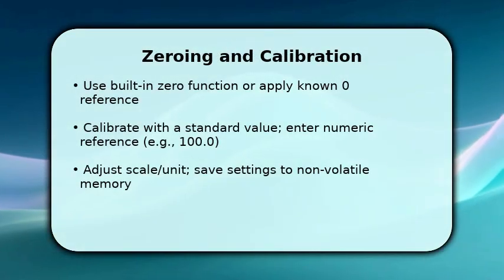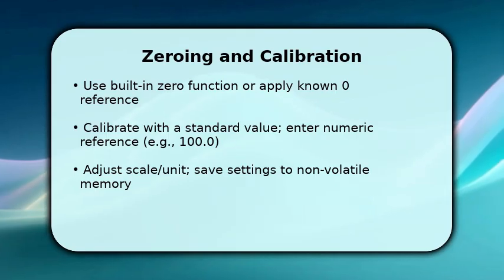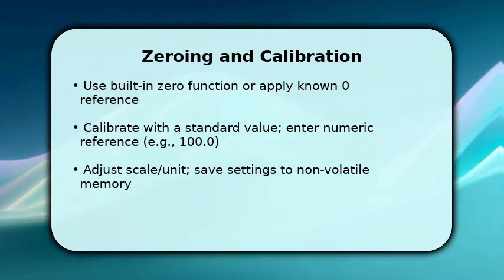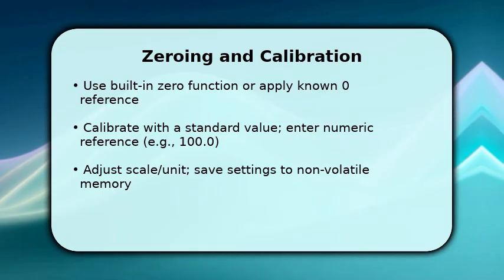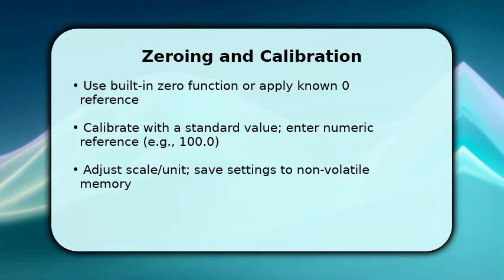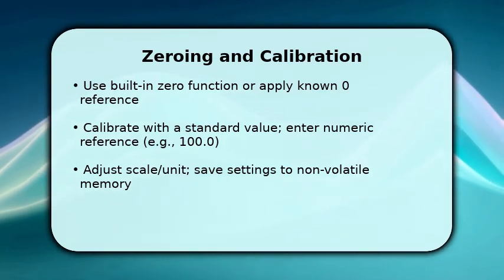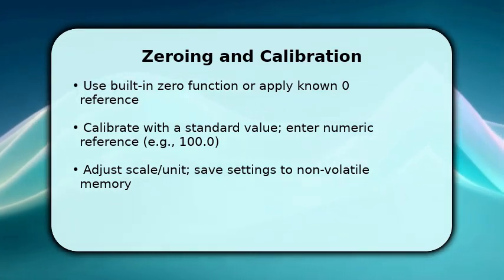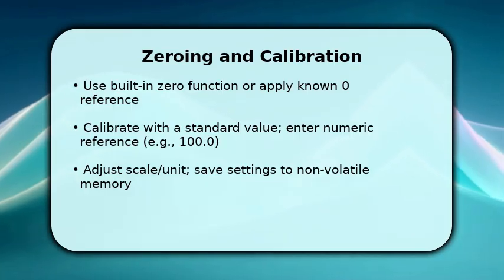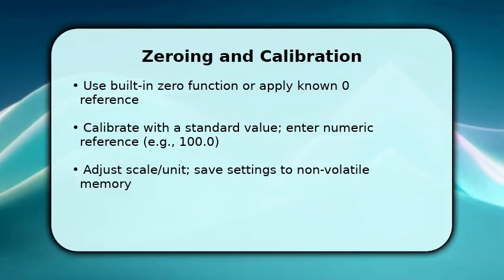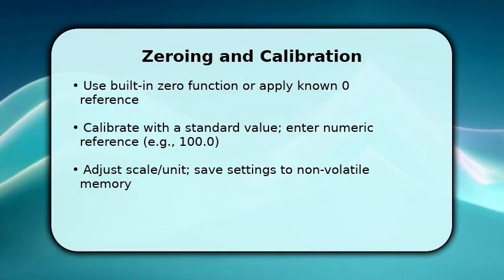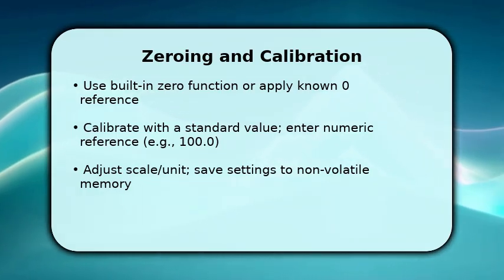You now focus on zeroing and calibration because accuracy depends on both. First, use the built-in 0 function or apply a known 0 reference and confirm the display reads 0. This removes offset errors. Then calibrate using a standard reference value, enter the numeric reference like 100.0, and follow the unit's prompts to complete the 2-point or single-point routine.